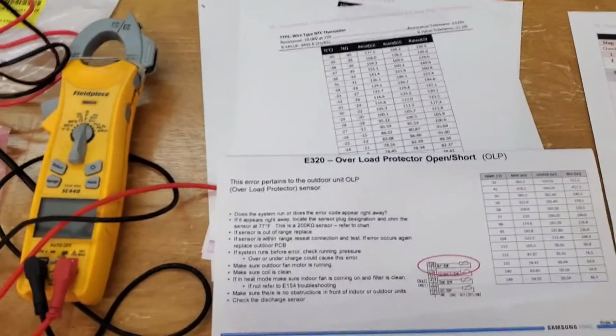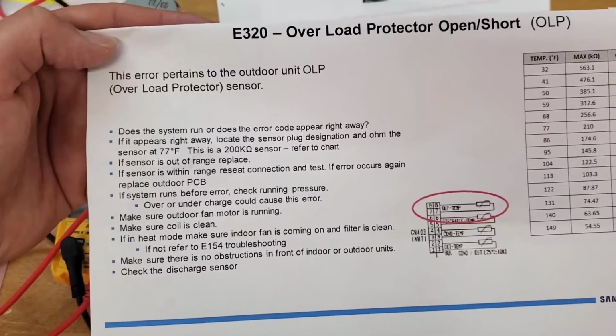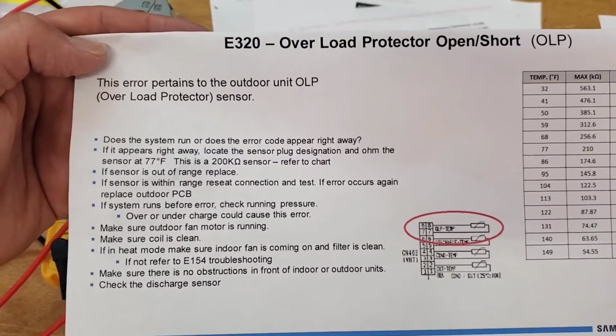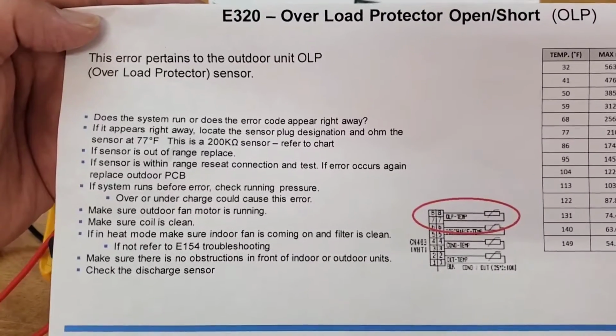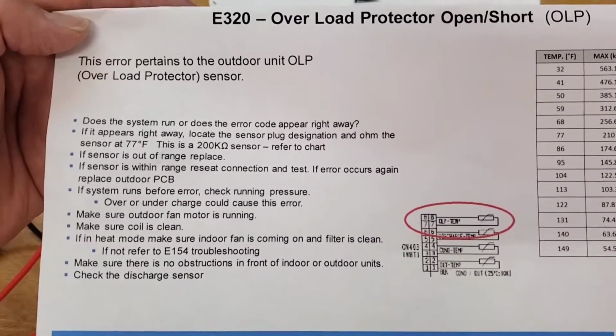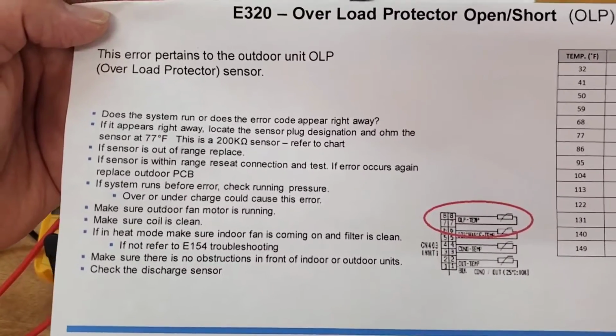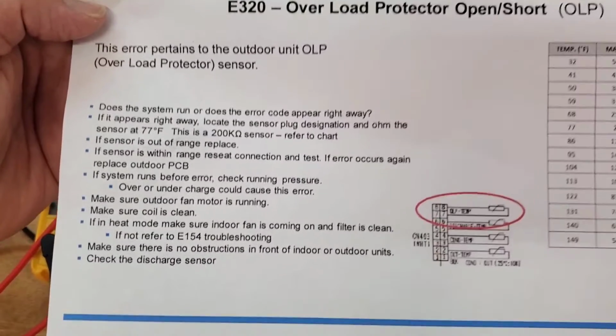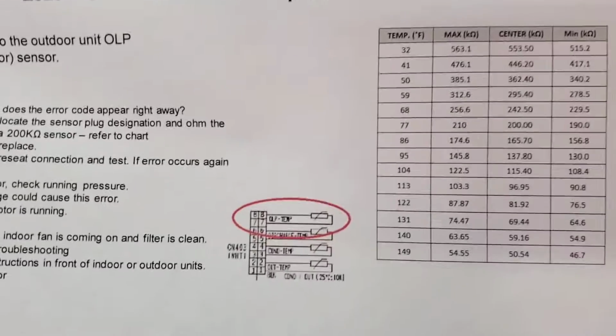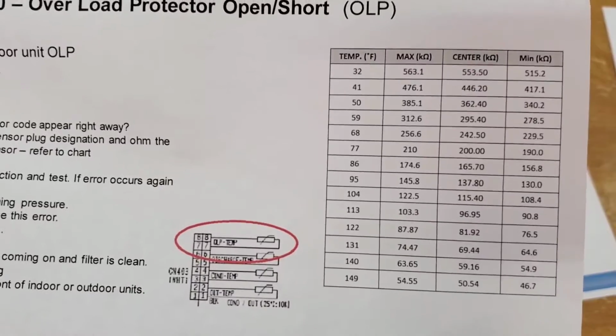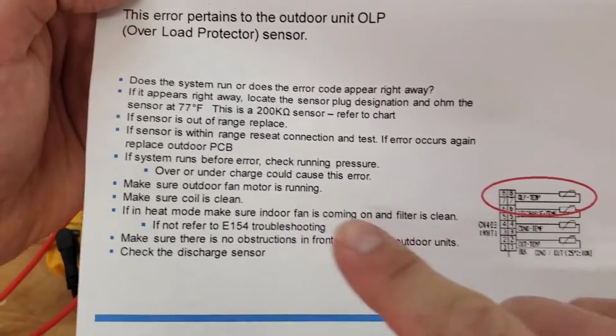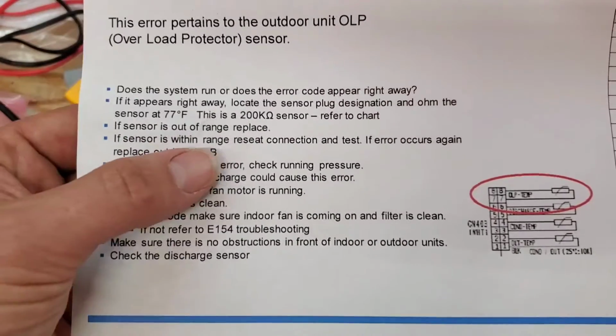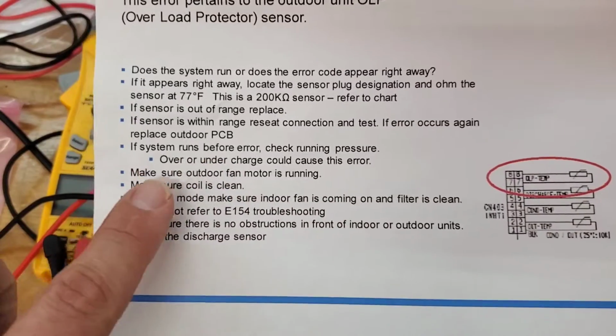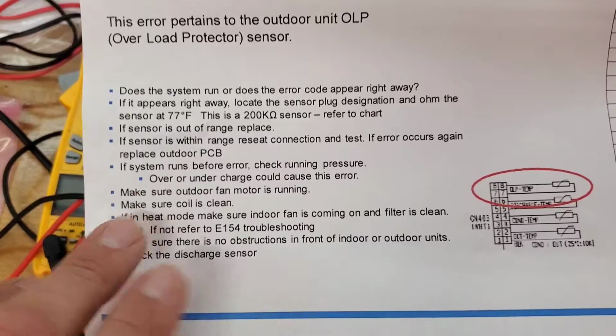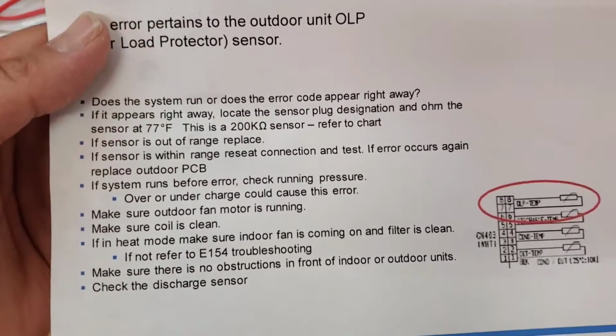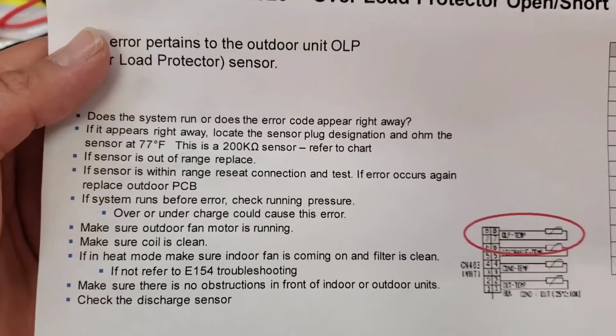So first let's talk about what you experience with the code. E320 means overload protector sensor or overload protection. Does the system run or does the error code appear right away? You need to know that. If it appears right away, locate the sensor plug designation and ohm the sensor at 77 degrees. Well, it may not be 77 degrees, so you'll just want to refer to the chart and look at the different temperatures and what the resistance should be. You have a minimum, a centered, and a maximum resistance reading that you should have. If the sensor is out of range, replace it, of course. If the sensor is within range, reseat the connection and test. If the error occurs again, replace the outdoor PCB. But first, before you do that, there are a couple of things you need to know, but that is the sequence you need to be adhering to when you have an E320 issue.